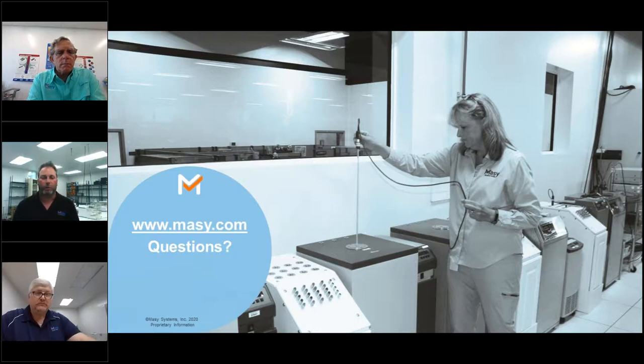For guard banding on lower level process equipment, where an accredited cal might not necessarily be required, I'd refer back to the slide I talked about earlier. I don't think guard banding is required for everything. I would definitely use it for primary standards and working standards with the same mentality I outlined for accredited cals. Beyond that, use your best judgment or consult someone like myself or your calibration provider about whether you need that level of cal or guard banding for a given piece of equipment.